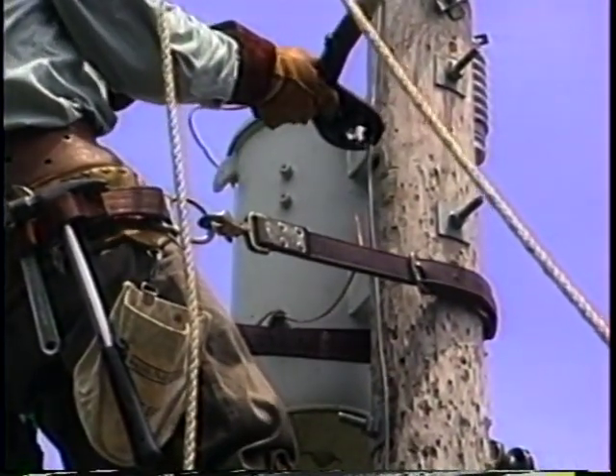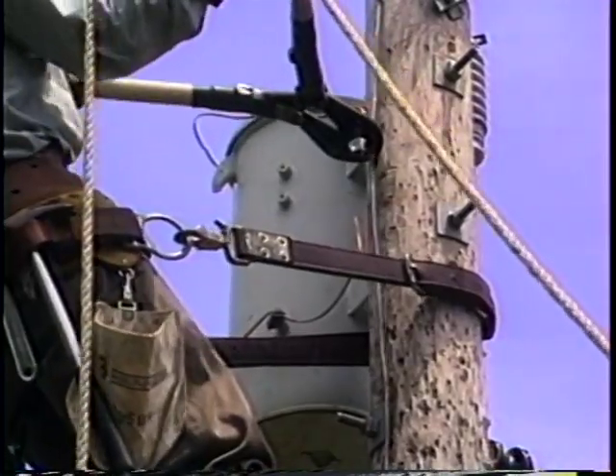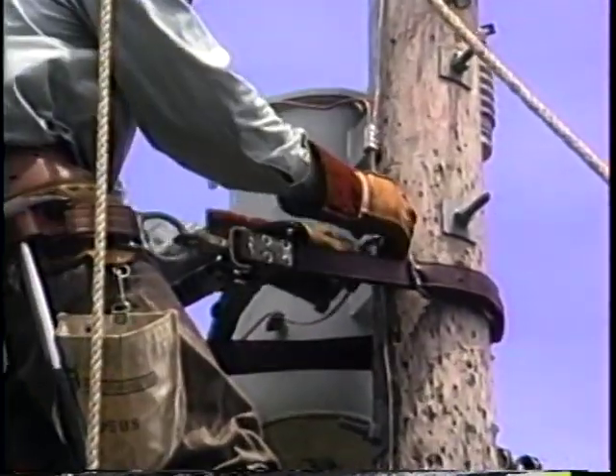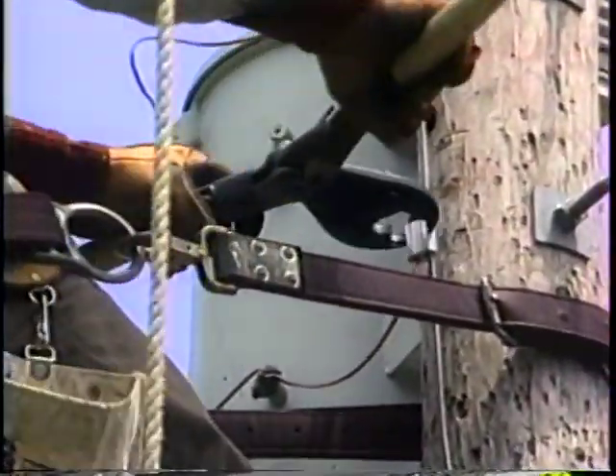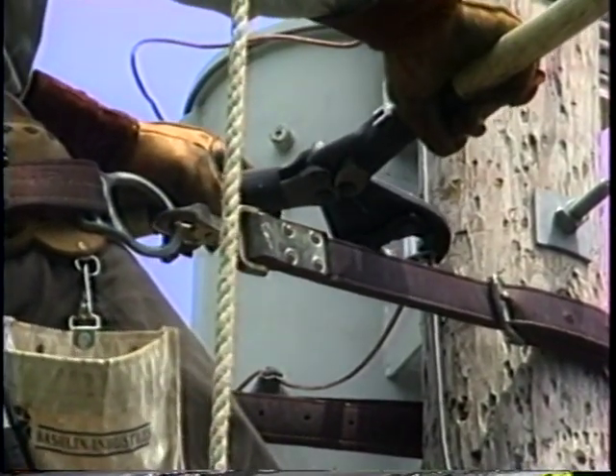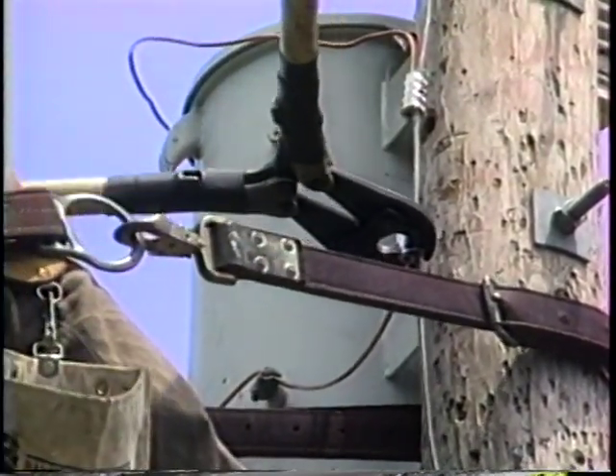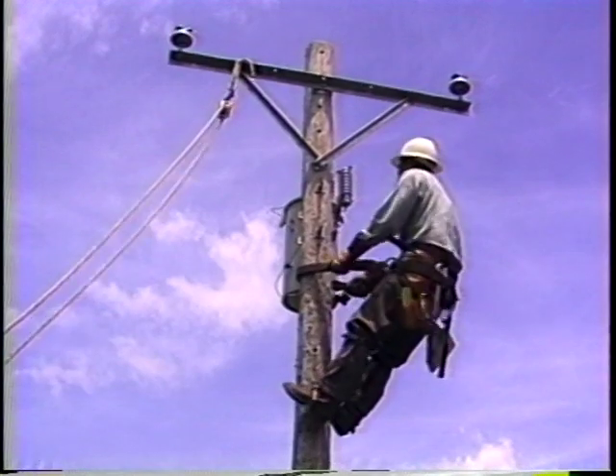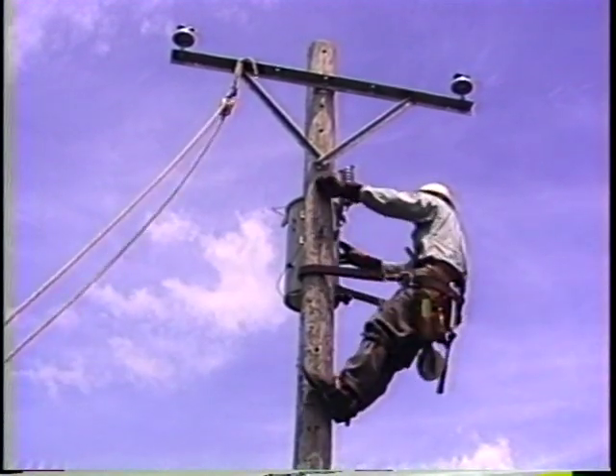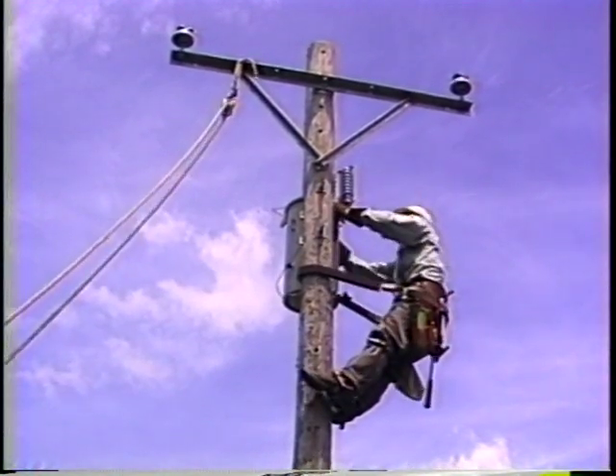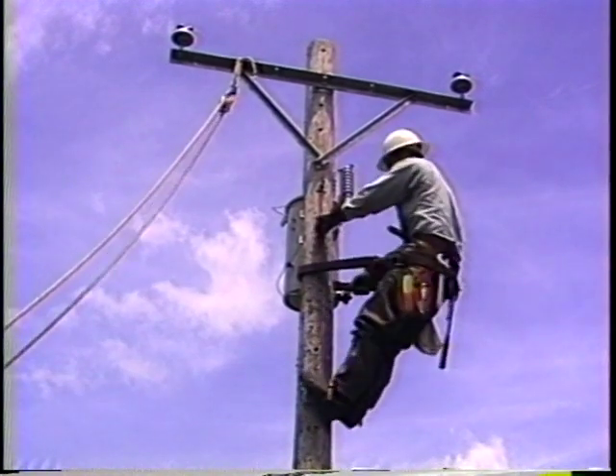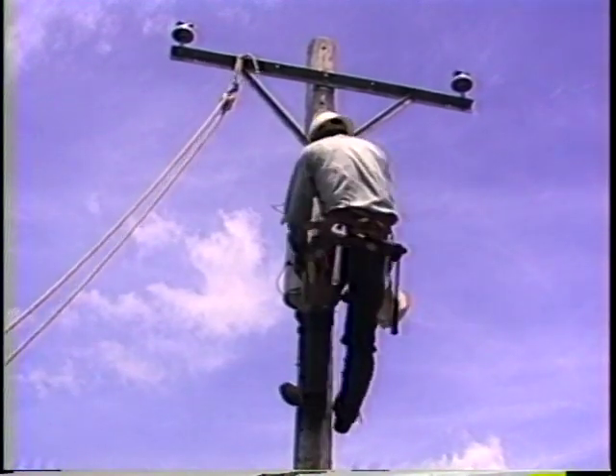Both transformer grounding conductors are connected to the pole ground. This provides two grounding paths from the transformer to the pole ground. Before climbing down, the lineman inspects his work and that of others. This confirms that all work has been properly accomplished.